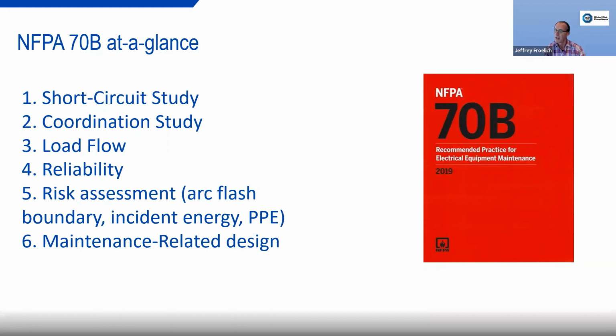And in there, it states annual frequency for infrared inspections, or more frequently based on a variety of different potential anomalies, loss experience, installation of new equipment, other environmental changes, operational conditions, load conditions. So you might end up doing it as frequently as monthly, quarterly, semi-annual. So it's a great standard, and there are others as well, but it's definitely one of the leading ones, if not the most important in North America.